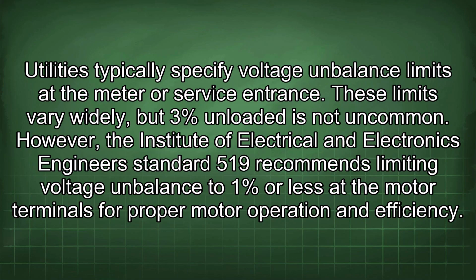Utilities typically specify voltage imbalance limits at the meter or service entrance. These limits vary widely, but 3% unloaded is not uncommon. However, the Institute of Electrical and Electronics Engineers Standard 519 recommends limiting voltage imbalance to 1% or less at the motor terminals for proper motor operation and efficiency.